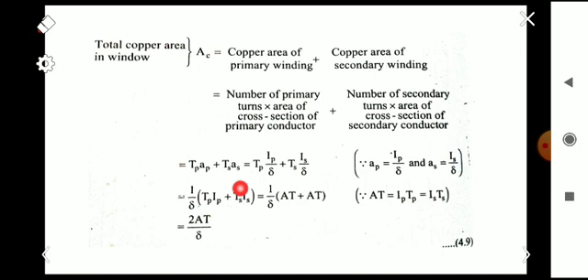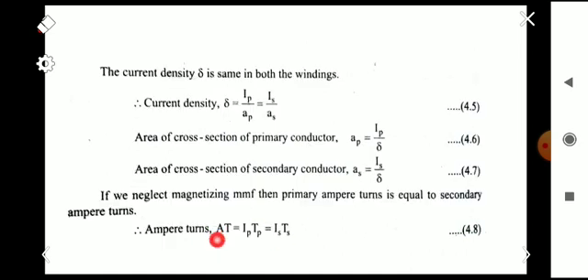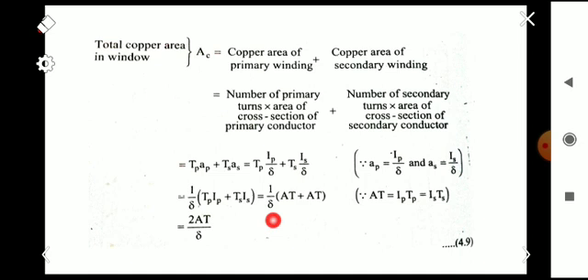Substituting A_p = I_p / δ and A_s = I_s / δ into the expression, we get A_c = T_p × (I_p / δ) + T_s × (I_s / δ). Taking 1/δ outside gives A_c = (1/δ) × (T_p I_p + T_s I_s). Since the ampere-turns on both sides are equal to AT, we have T_p I_p = T_s I_s = AT. Therefore, A_c = (1/δ) × 2AT = 2AT / δ.